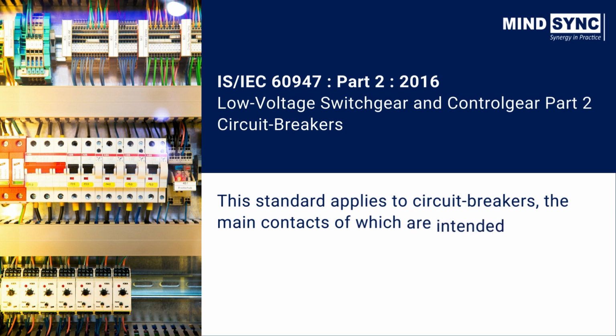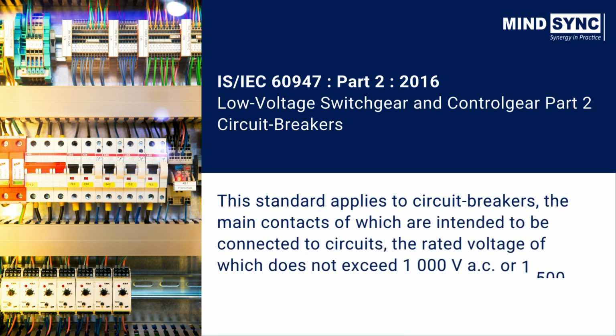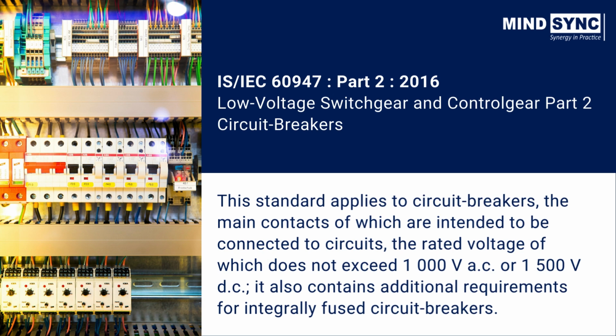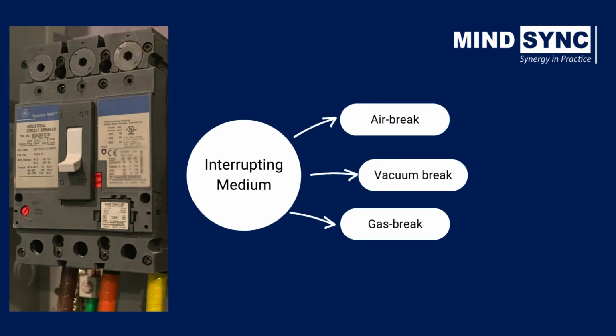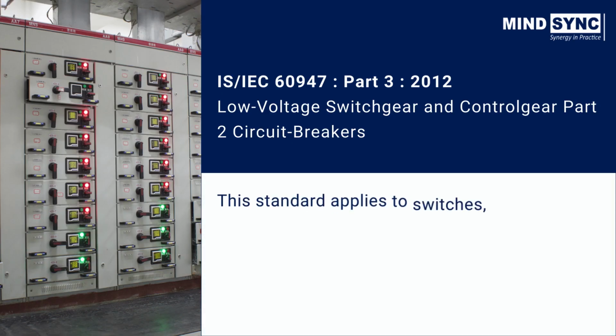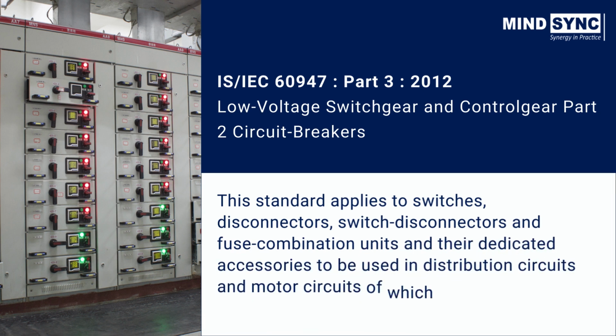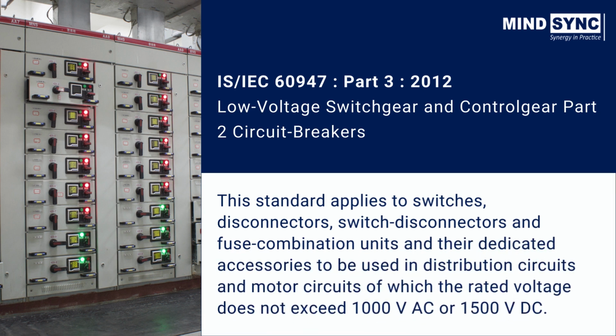The first standard pertains to low voltage switchgear and control gear part 2 circuit breakers, which applies to circuit breakers whose main contacts are designed for circuits with a rated voltage not exceeding 1000 volts AC or 1500 volts DC. The interrupting mediums include air brake, vacuum brake, and gas brake. The second standard also falls under low voltage switchgear and control gear part 2 circuit breakers. It covers switches, disconnectors, switch disconnectors, fuse combination units, and their dedicated accessories for distribution circuits and motor circuits with a rated voltage not exceeding 1000 volts AC or 1500 volts DC.